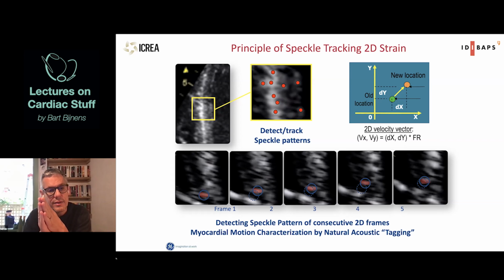But what I then say is another advantage, in brackets, of speckle tracking would be that it's angle independent. But keep in mind, angle independence in ultrasound, in cardiac ultrasound, where you have sector images, does not exist. Because by the fact that you're using sector imaging, that means that the deeper you go, you actually have a different lateral resolution, and always the resolution on the scan line is much better than the lateral resolution at any position.